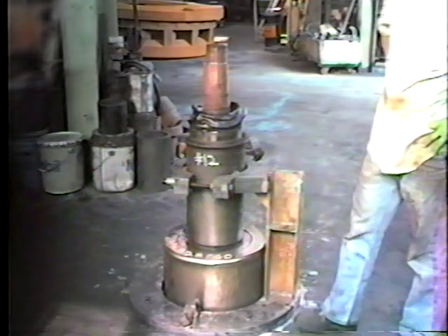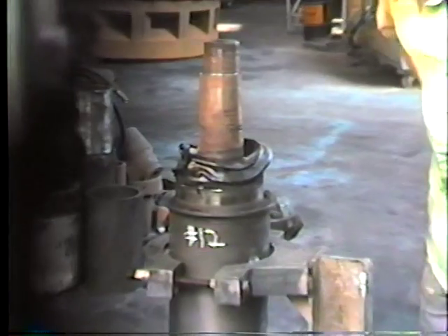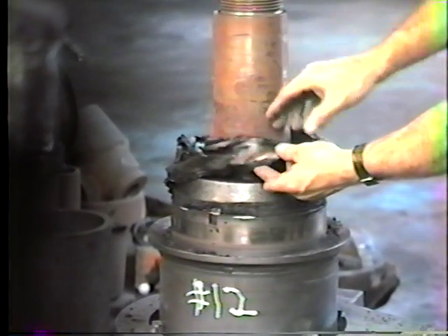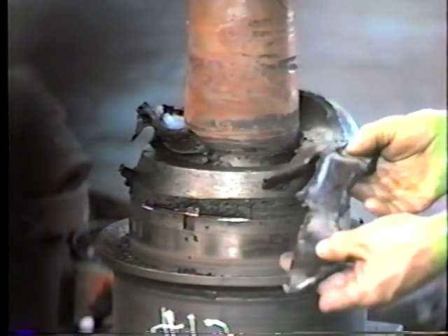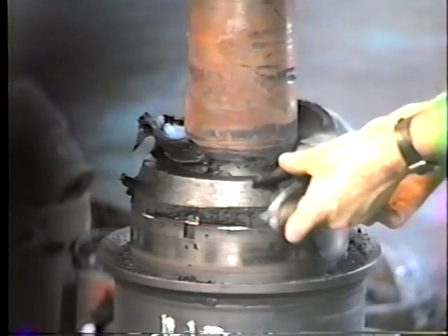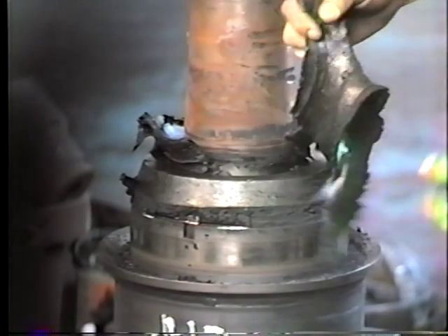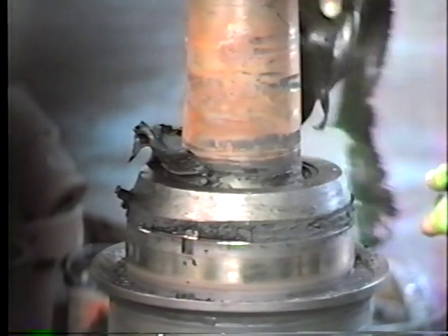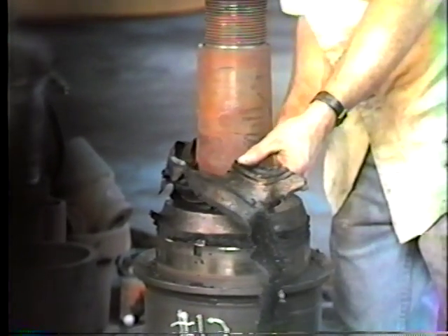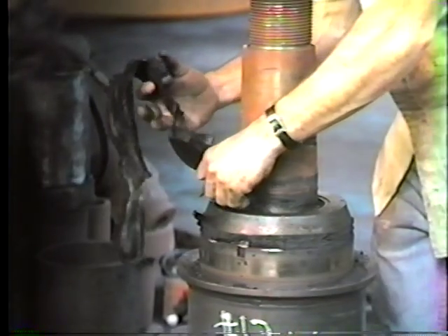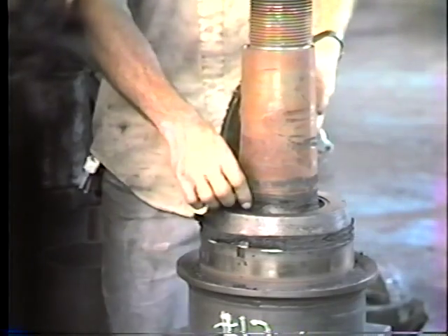This number 12 journal, this is the last of the journals. Would you please show me that grease? Is it rubberish or what is it? That's the SP3 grease? Right. Okay. So this is the last of the journals that had SP3 and has been in operation now for about 8 to 9 months.